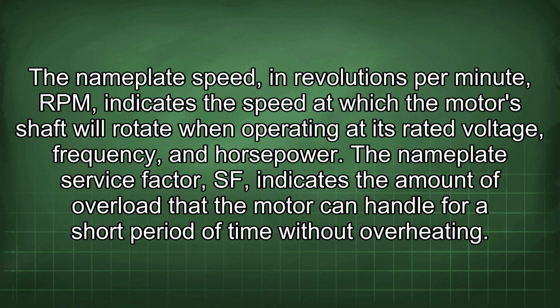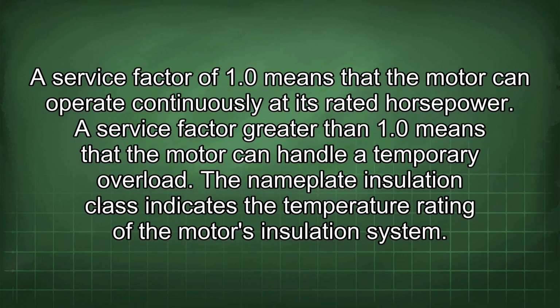The nameplate service factor, SF, indicates the amount of overload that the motor can handle for a short period of time without overheating. A service factor of 1.0 means that the motor can operate continuously at its rated horsepower. A service factor greater than 1.0 means that the motor can handle a temporary overload.